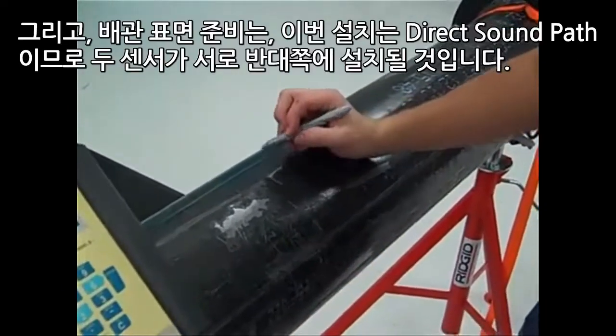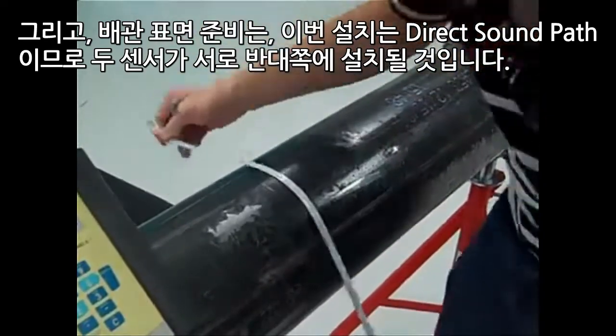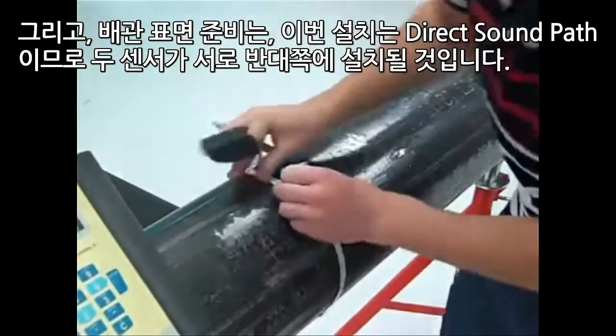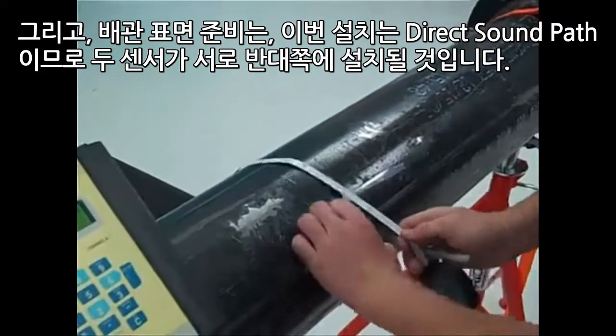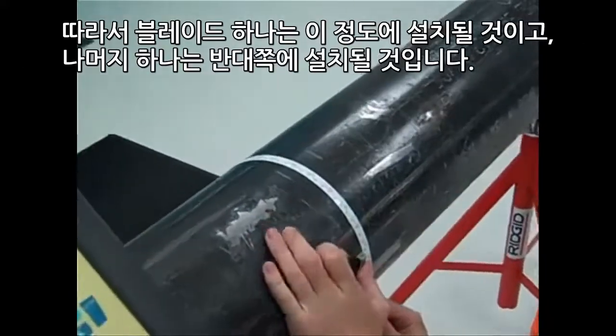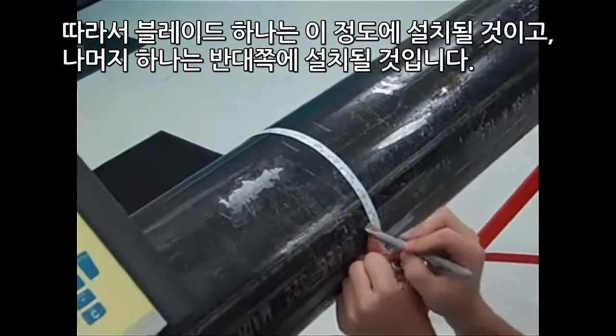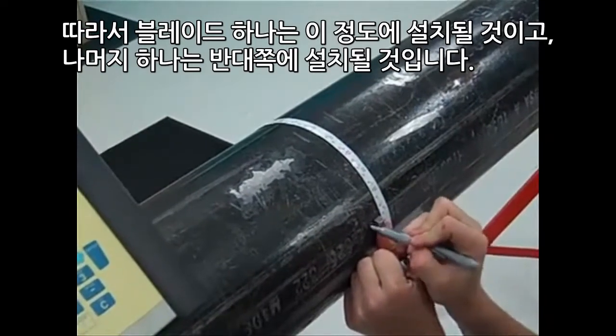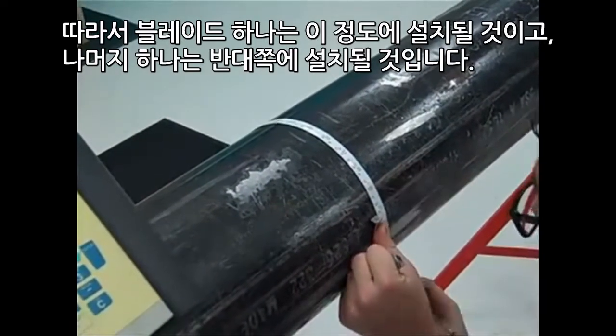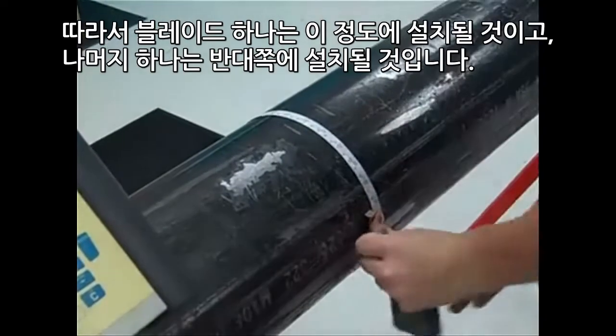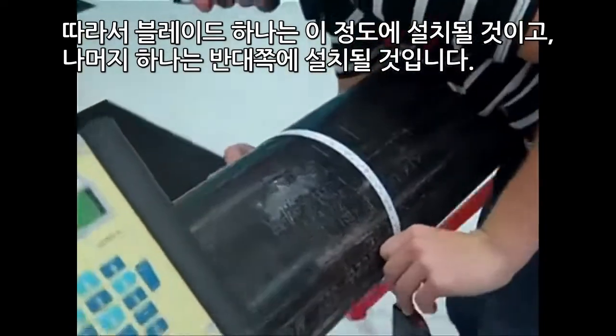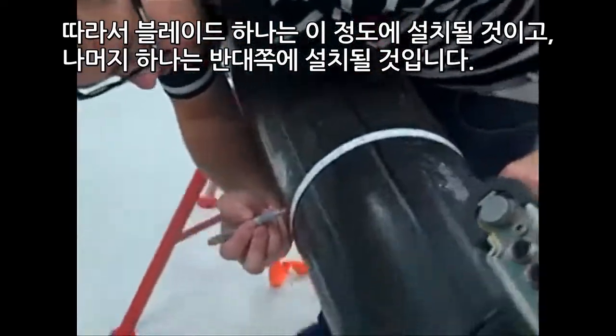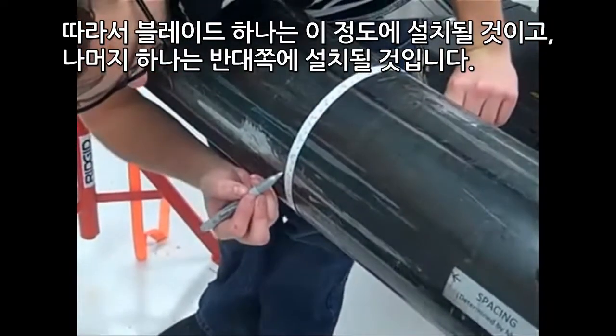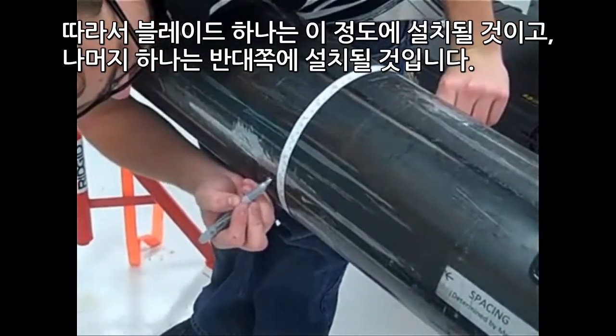And your pipe preparation, since this is direct, this is going to be a direct mounting style. They have to be on the opposite sides of the pipe. So we're going to install approximately 1 blade right here, 27 inches, and 1 approximately right here, 14.